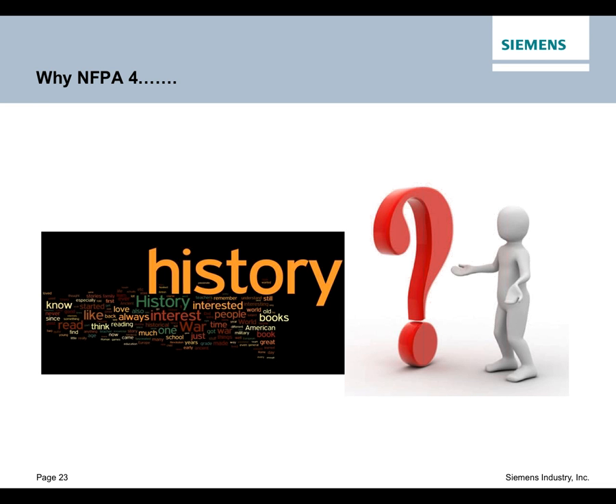And that not only has been the industry accepted way of doing things, but recently, within the last three years, NFPA has come out with a directive that says those of you doing design and installation and service work within fire alarms or sprinklers, your job is to only stay within your scope of work area. As a matter of fact, NFPA is now saying we can't go out and touch the fire sprinkler system or the building control system or the security system within the scope of 72. So they have also drawn this line of demarcation, we'll say, at that relay type of situation.